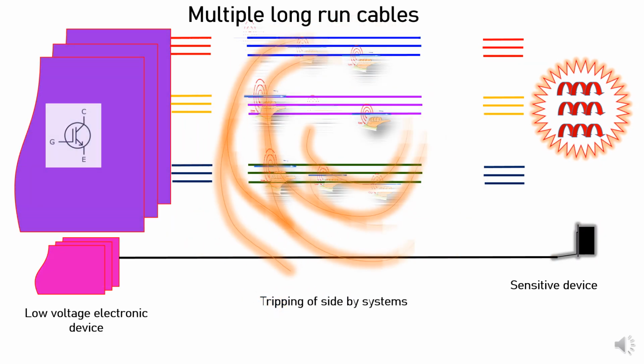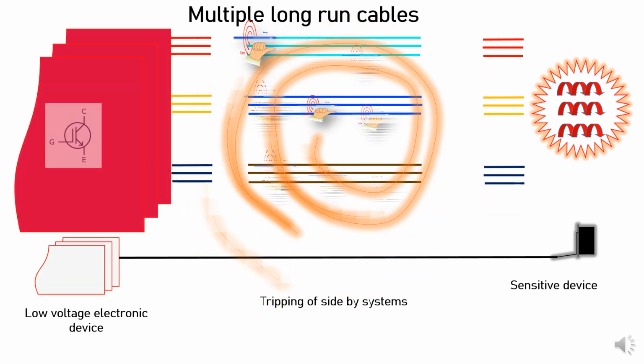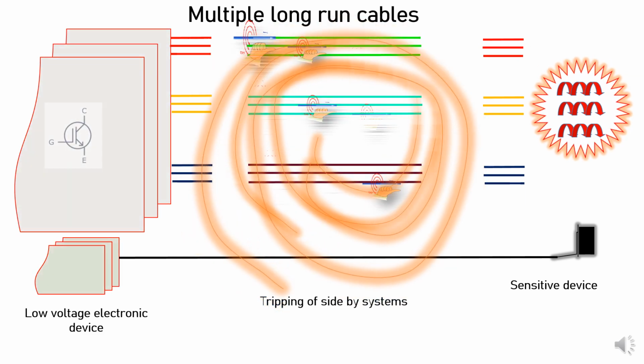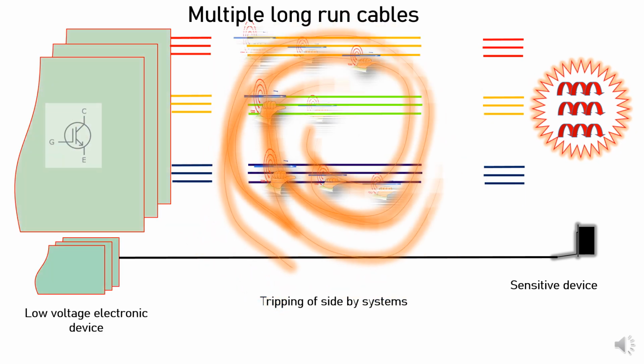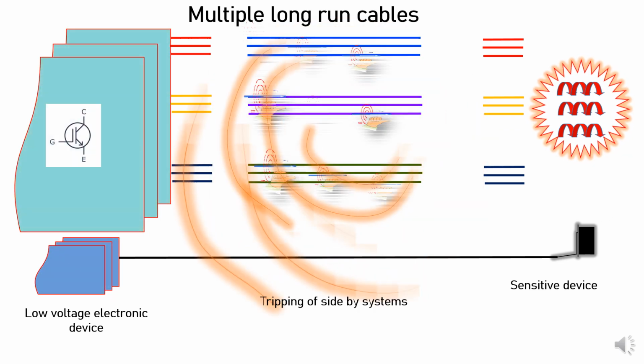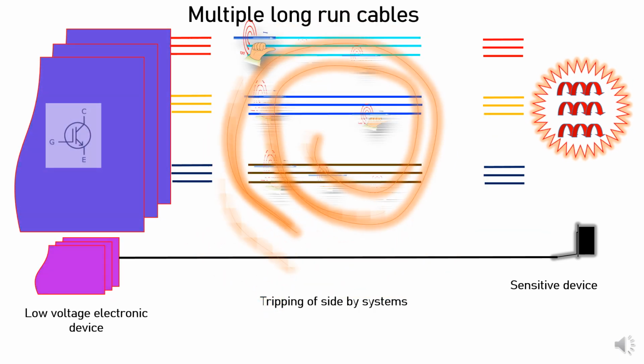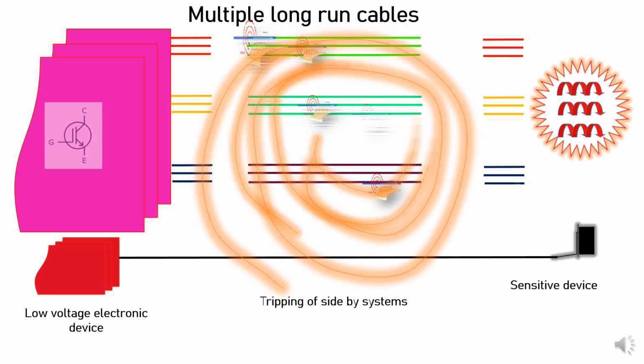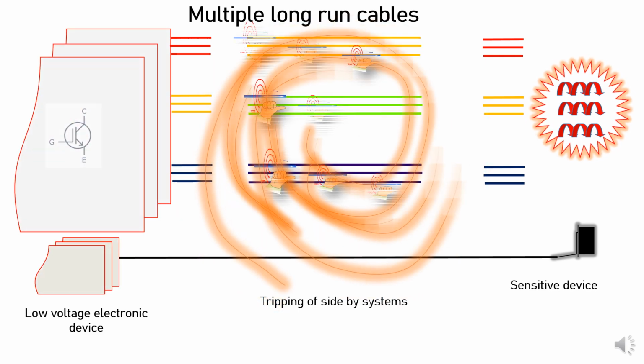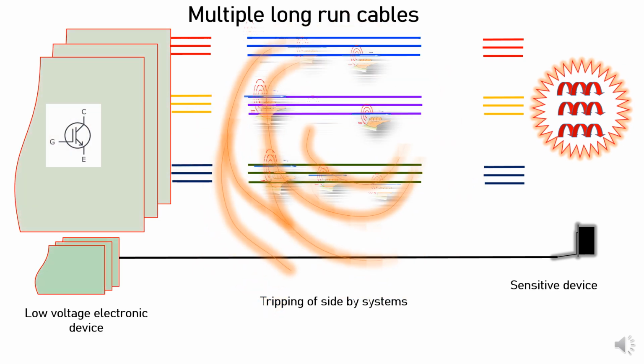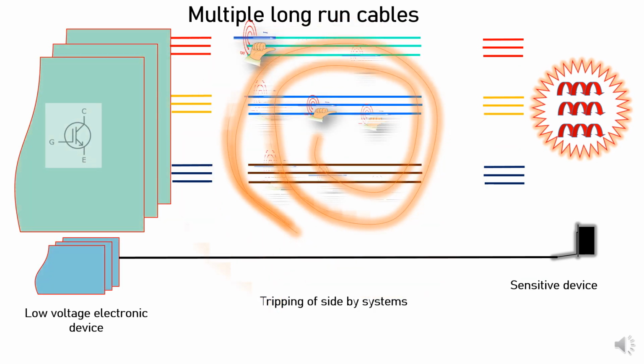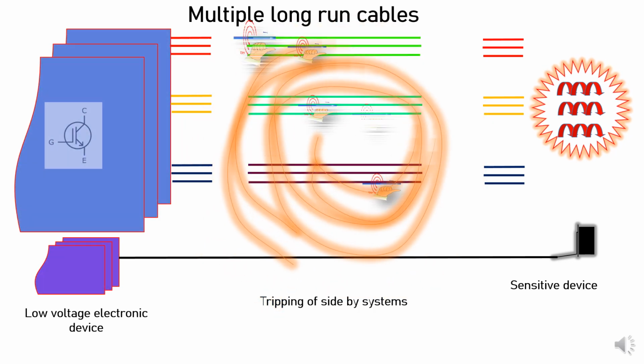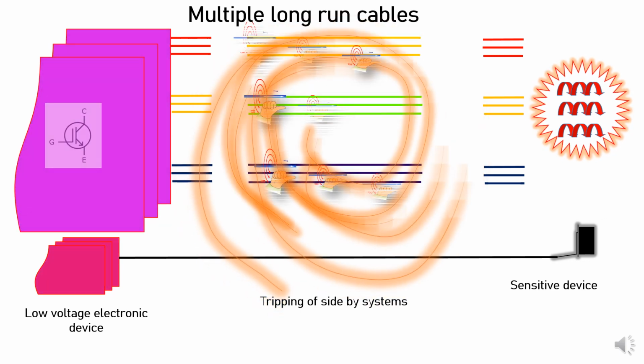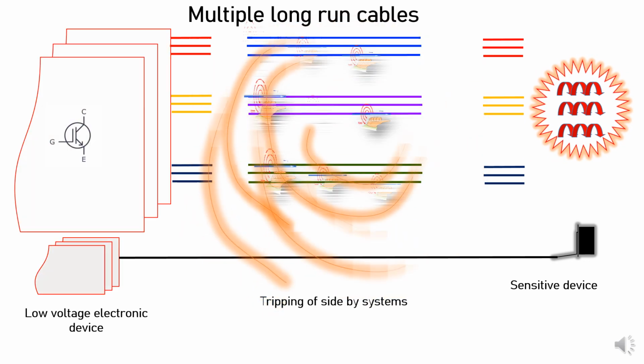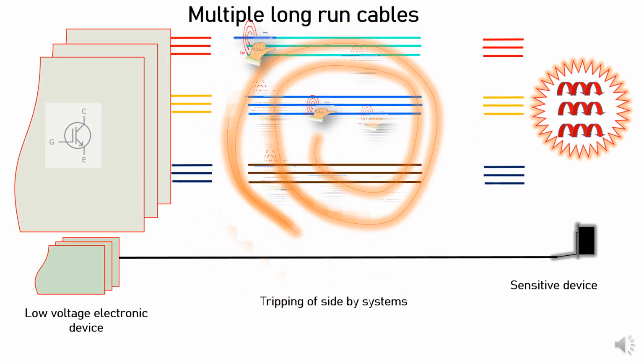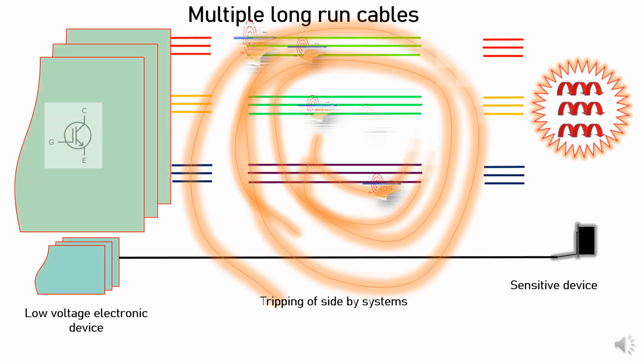Now you can see the tripping of the side by system, you will not find anything wrong, and if you reset this electronic device, it will work for a few days, a few months, depending on how much magnetic field is being generated. Indirectly it depends on the motor load, at what load the motor is supposed to run. If the motor is running at a lesser load, the field is not that strong to affect the side by cable. One beautiful day, the load will be increased, it generates a strong field and it will trip the electronic device. You will never find a single fault in this type of arrangement. That is the biggest headache for the user.